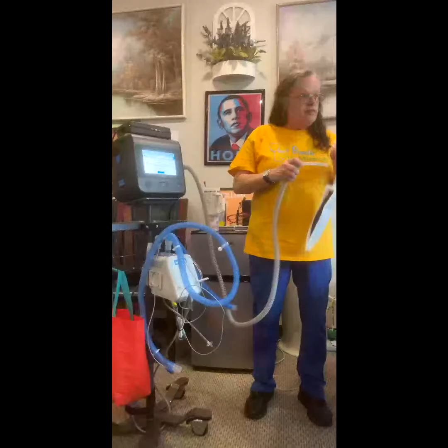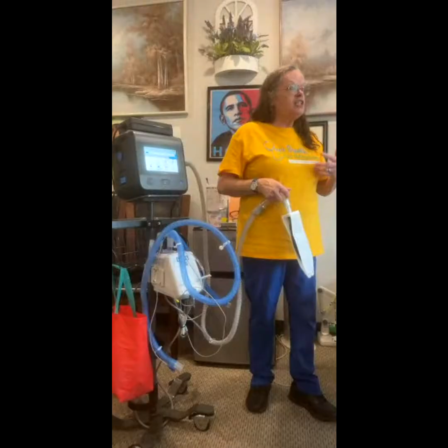Yep, it failed. So that means it's only going to do it with the regular circuit, and you have the isolation valve off. I really don't see the reason for doing that unless there's a problem, like you're changing from a pediatric to an adult circuit or from an adult circuit to a pediatric circuit. For the most part, we don't change our circuits but every other week, because if you continuously change your circuits, you can instill bacteria or germs by changing it. That's why we use sterile water as well.